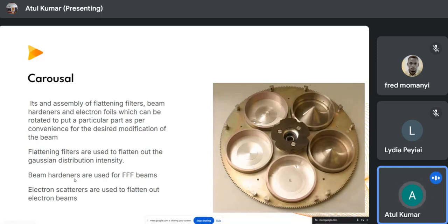It's like a torch. When you turn on your torch, the central part is the most lit one, having the highest intensity. But if you put butter paper on it, you have a more or less uniform light coming out from the torch. The same way, you have to stop the center part to a greater extent than the radial part. That is why this kind of shape is used to flatten the beam. After the beam passes through this shape, the output is more flattened. So this is why it is called a flattening filter.